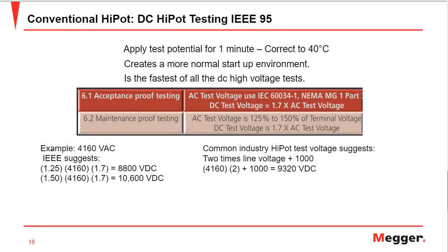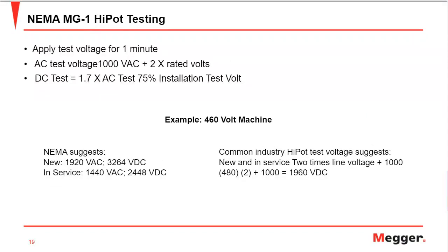There is also a common industry high-pot test voltage, where we just multiply the line voltage by two and add 1000 to it to get our test voltage. So this was IEEE 95. We have another standard from NEMA. It also suggests that our DC test voltage should be 1.7 times the AC test voltage. If the motor is already in service, we just add a factor of 0.75, or 75% of that calculated test voltage.